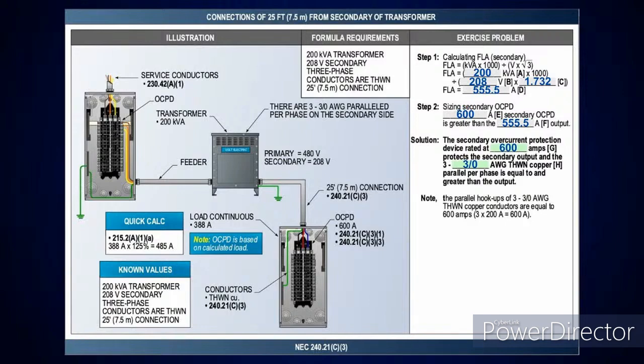Like this one here, this is 25 foot. I do the same calculation. I've got a 200 kVA transformer. I'll multiply it by 1,000. It's a 208 volt secondary here with three phase, so I multiply it by 1.732. Do my calculation. The full load amperage is 555 point something amps. The next size above that is a 600 amp overcurrent device. Now I'm going to parallel this one 3 times. We're telling you to do it 3 times.